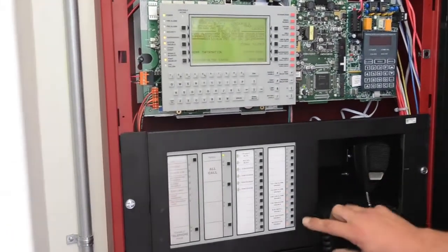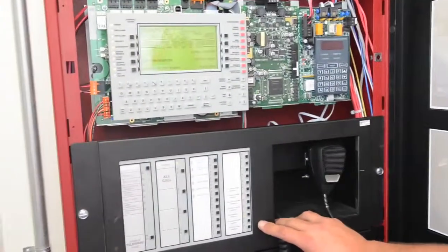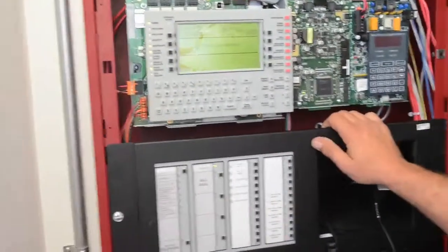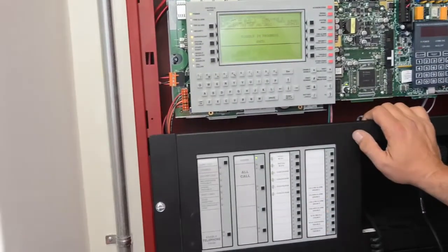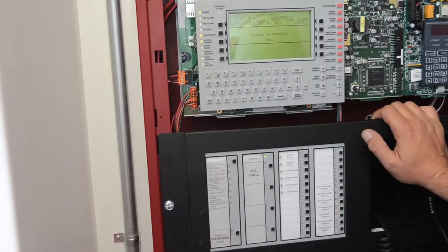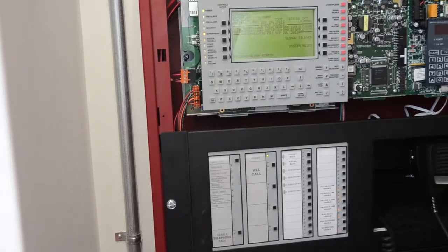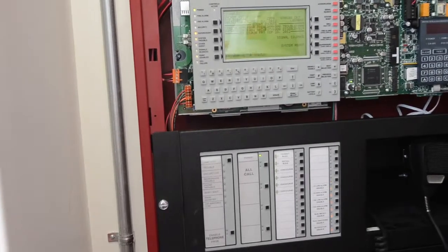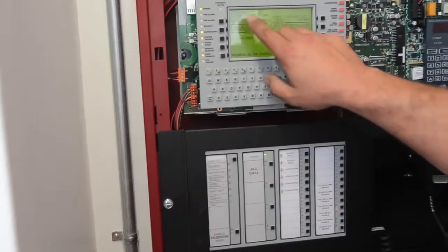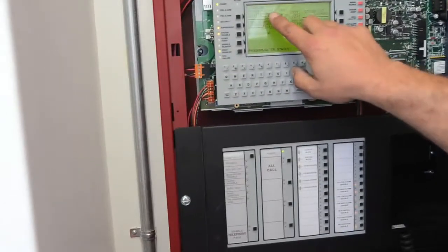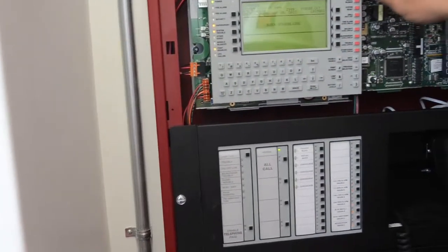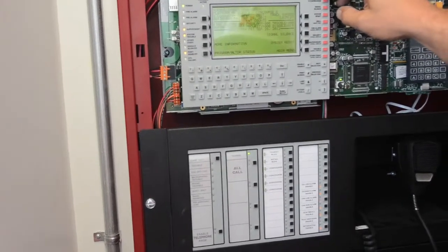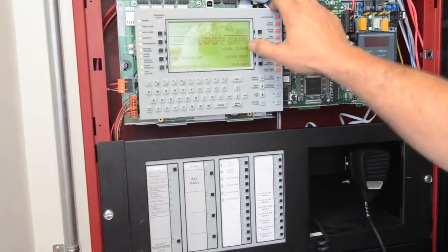There are a few other disable functions we programmed into the system. For testing, we have a notification disable. Selecting this button will disable all your speakers and strobes throughout the entire site. This allows you to go through and test the system without having all the bells and whistles go off, and to perform a complete functional test of the system. In addition, it's giving me some trouble conditions now, letting me know the points are disabled. I just acknowledge, and that silences it. It's just letting you know that there are troubles on the system, and our disable points indexed up.